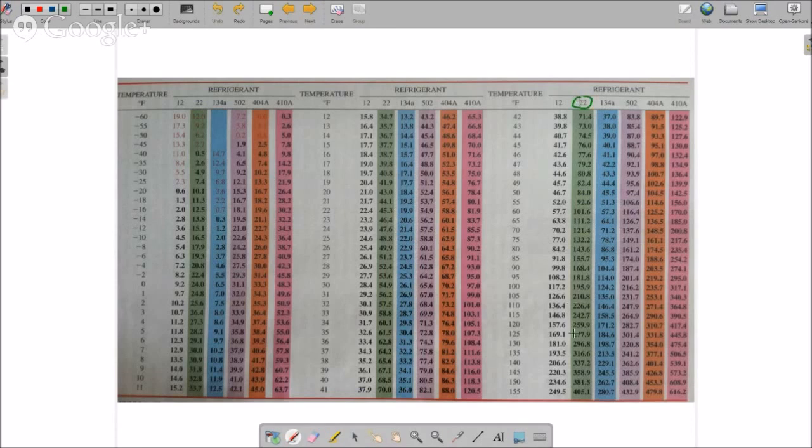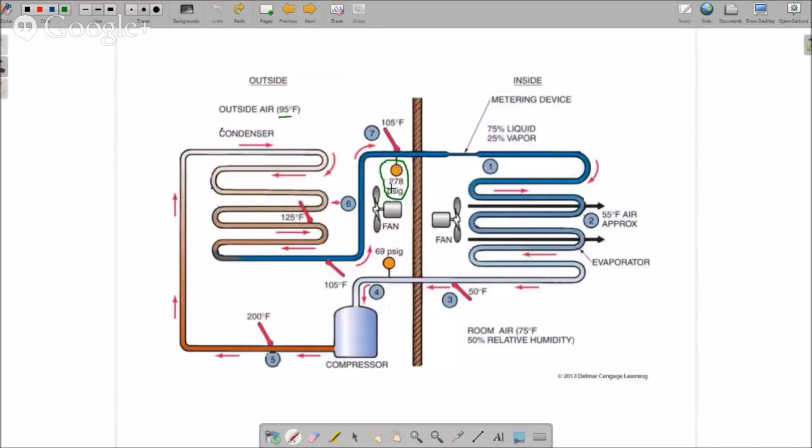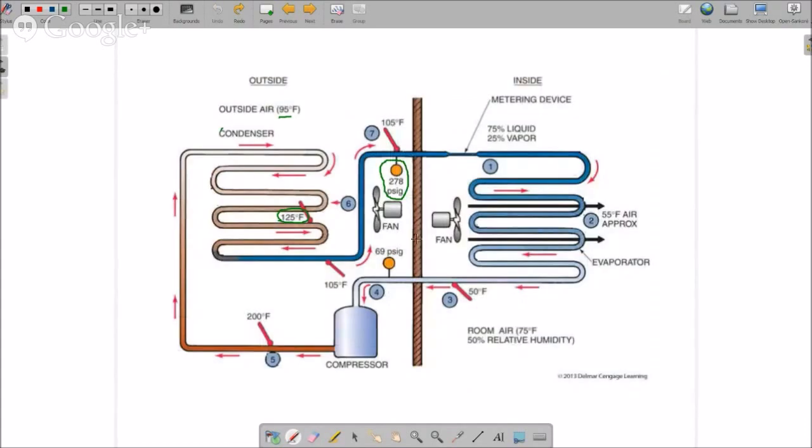We look at 278 psi is equivalent to 125 degrees, just like in our diagram over here. So it is 125 degrees. Now remember when you have your high side gauge on the system and you're looking at this pressure and converting it over to the temperature, just like we did, you'll notice that the pressure converts to 125 degrees Fahrenheit.